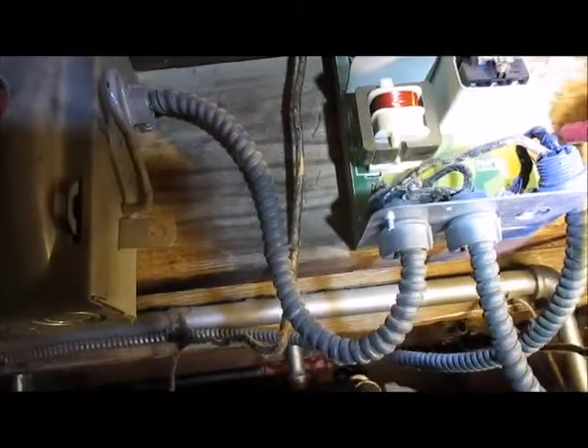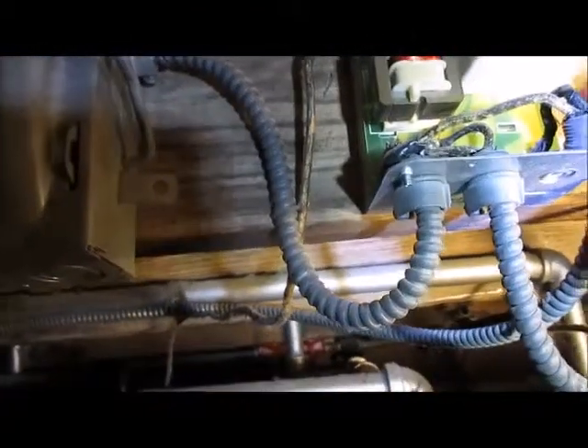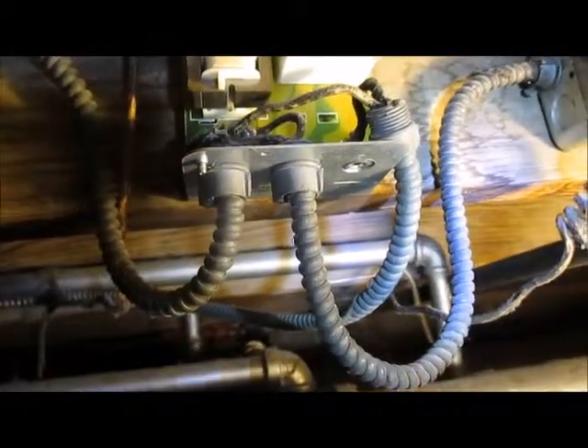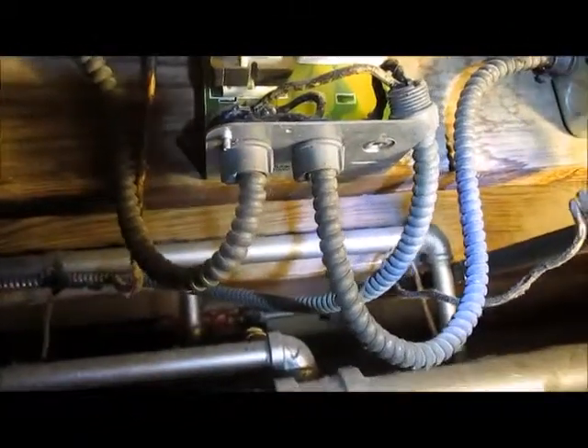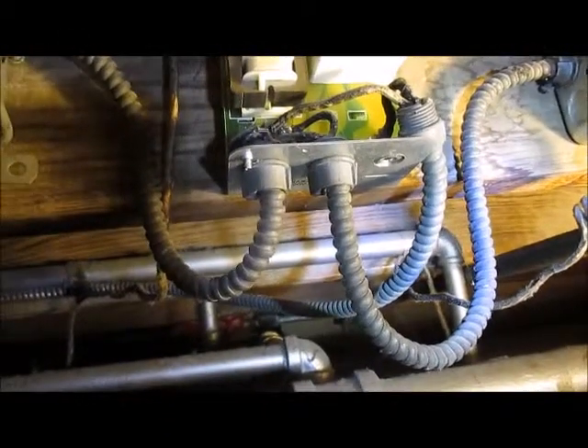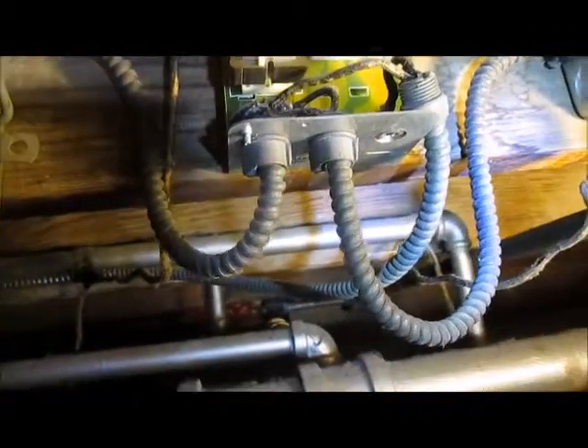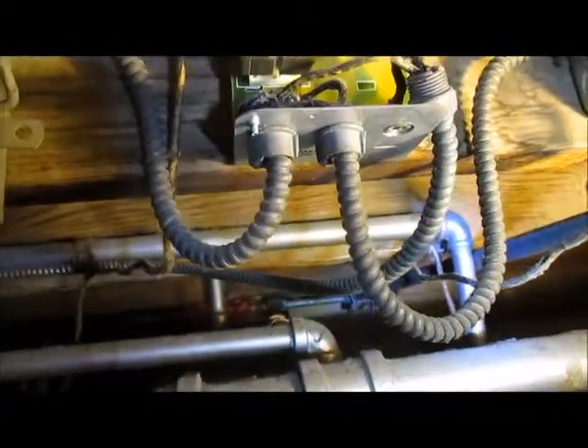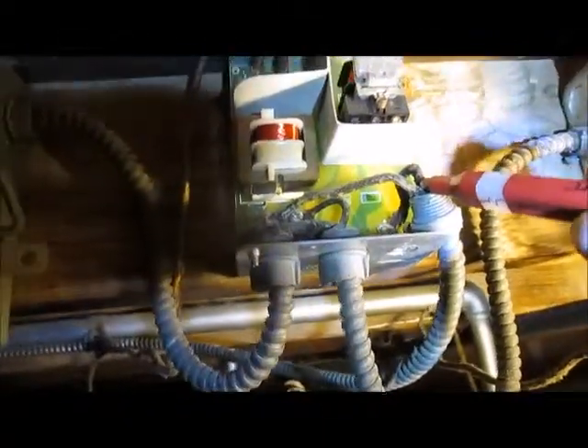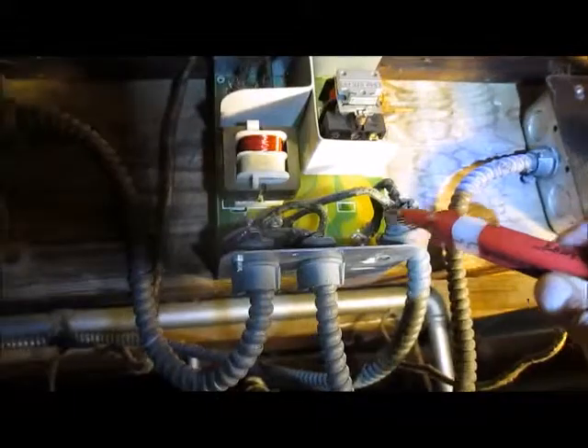If I were to get power here, I would go to the pump and test the power at the motor to see if the motor was working. If I'm getting power there but the motor's not working, that means the motor's bad. If I'm not getting any power here, that means the switch relay is bad.